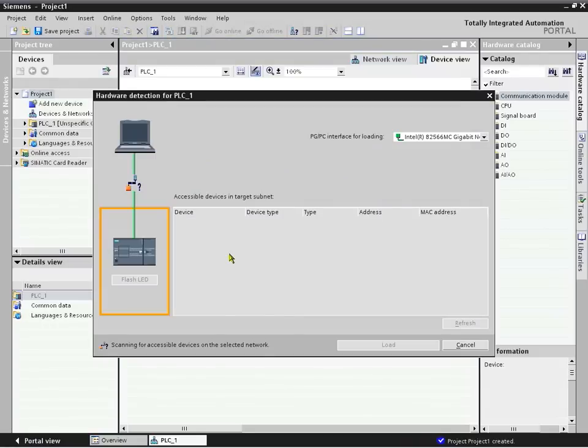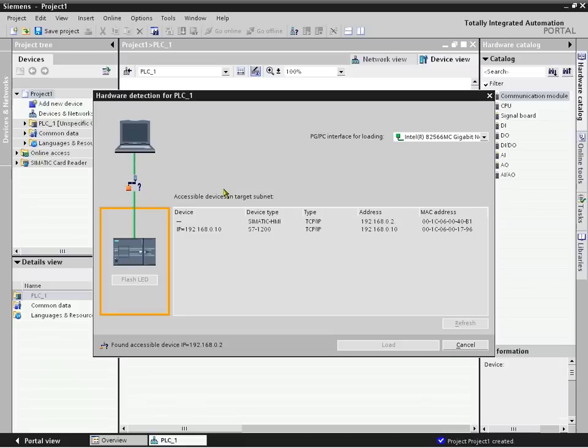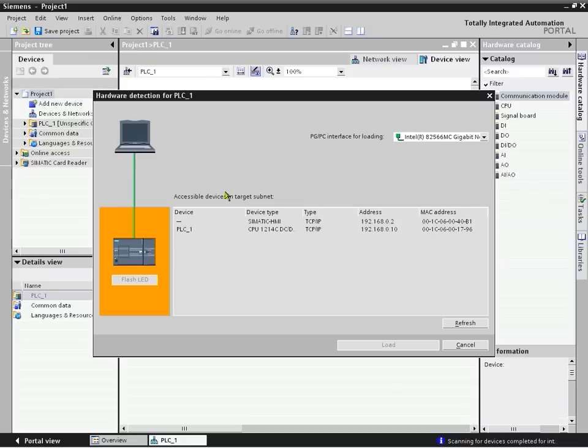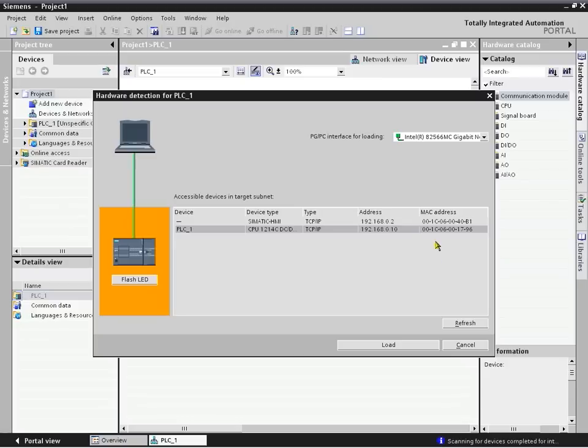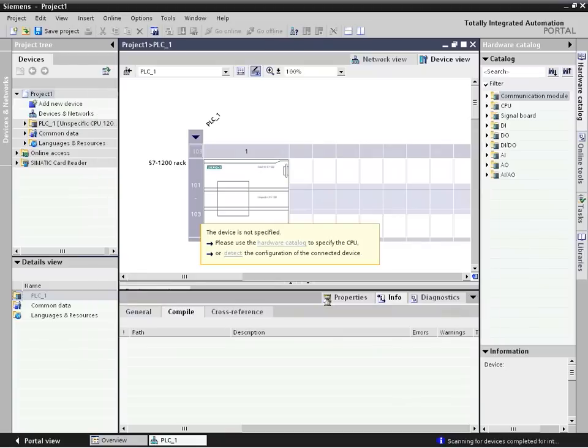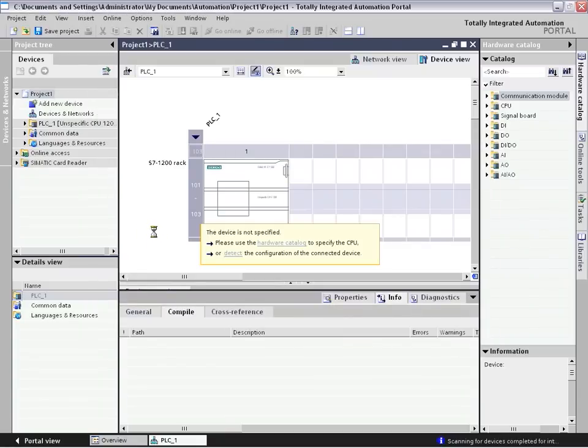So if we detect it, it's going out over Ethernet, and it's not worried about what the IP address of the PC is that's connected to it or the IP address of the controller. It'll bring anything up on the subnet of that particular LAN according to the MAC address. And then you're able to load it right from here. And if you had several controllers, you can specify which one you wanted to load into the configuration for your new projects.